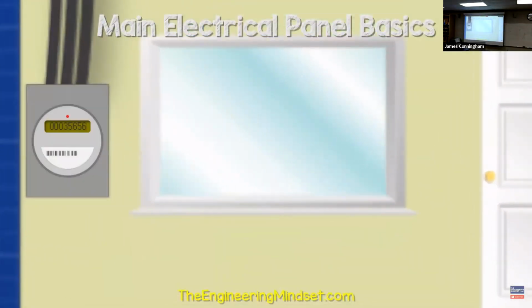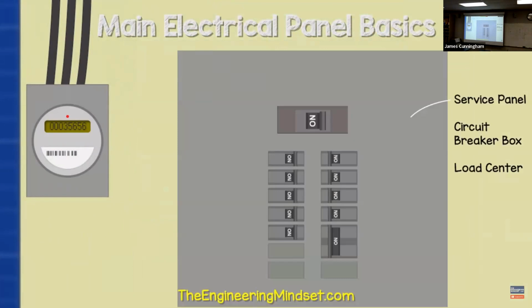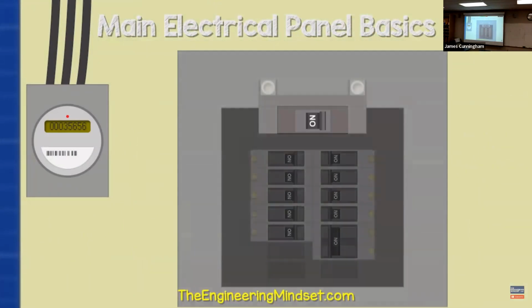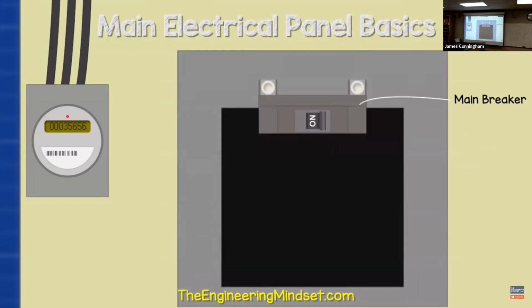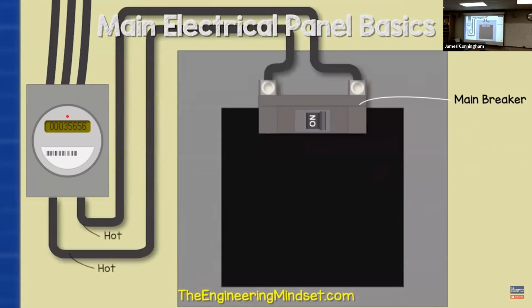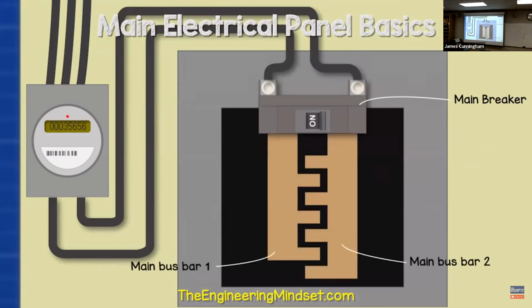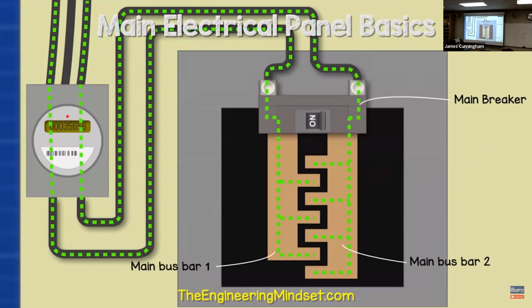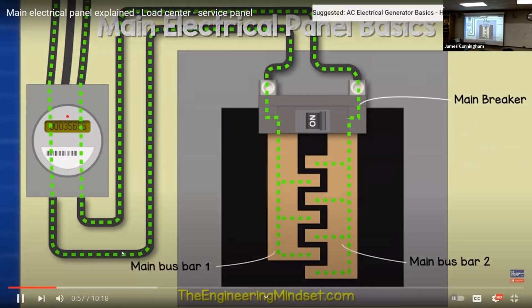So if we zoom into the property, we find a main service panel, which is sometimes called a load center or breaker box. If we remove the cover and look inside, we first find the main breaker, which is usually at the top of the panel, but it might be at the bottom. The two hot wires from the electricity meter will connect directly to the lugs on the main breaker. Coming out of the main breaker will be two main bus bars. These are basically exposed metal sheets which carry electricity to the circuit breakers. Notice I've shown the current going backwards and forwards.